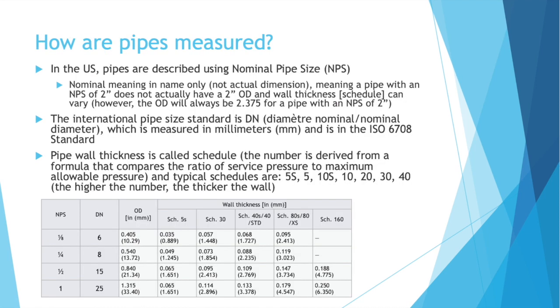How are pipes measured? When purchasing pipes or talking about pipe design, in the US pipes are described using the nominal pipe size measurement, NPS. Nominal means in name only, so it's not the actual dimension. A pipe with an NPS of 2 inches does not actually have a 2-inch OD, and wall thickness — called the schedule — can vary. However, the OD will always be 2.375 inches for a pipe with an NPS of 2 inches. The international pipe size standard is DN, nominal diameter, measured in millimeters, and is in the ISO 6708 standard.